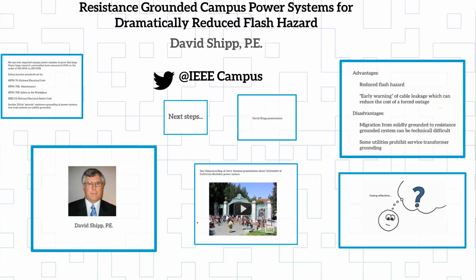The incident energy, just think, is proportional to I squared T, and then all the different equations that Tammy's worked up. But I start with I squared T, just so you get a reference point. It's actually not a square, but it's something less than that. But the point is, it gives you a concept of where to go. If I start with 20,000 amps squared times 0.1 seconds clearing time, that's a big number.